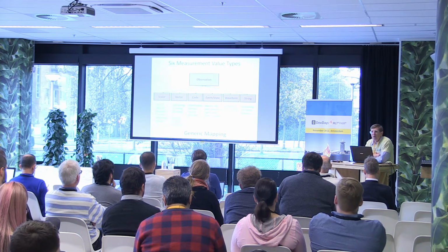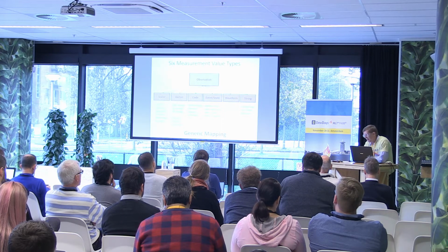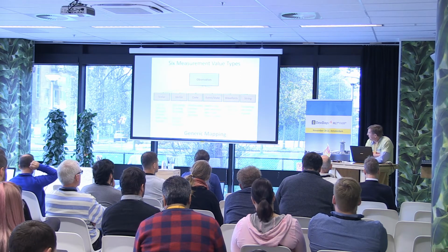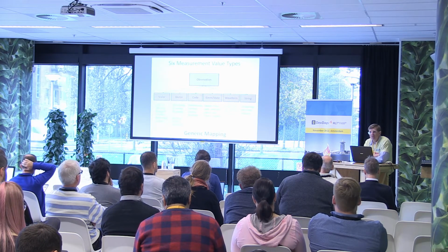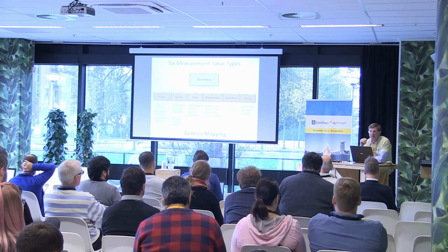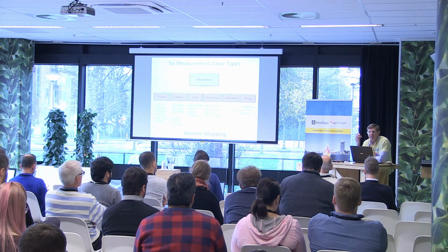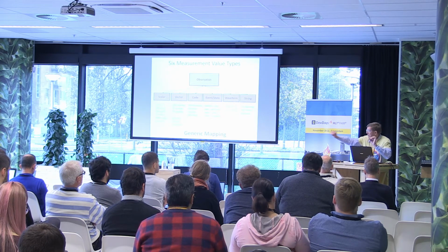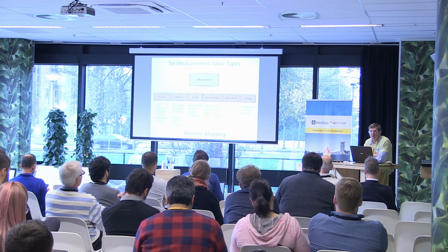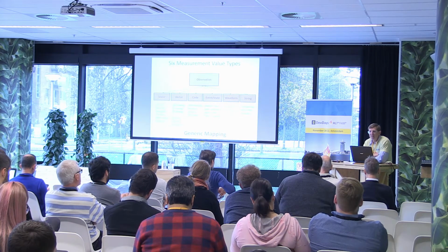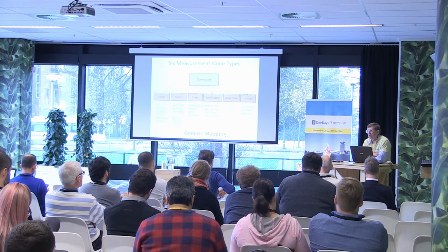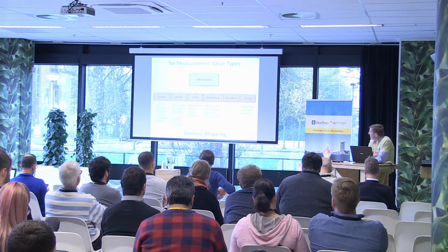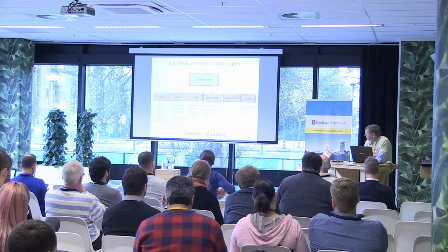And the other type of measurement are waveforms, ECG traces, for example. I've got one here that can take ECG traces, and you can upload those. Those types of measurements are strings of periodic data, and they can be a lot. For example, this thing takes 250 samples per second for 30 seconds, so we end up uploading something like 7,500 samples as a long string of data. Now, you could be really dumb and upload each one of them as an individual scalar, do 7,500 uploads to accomplish the transfer of the data. Not too smart. So every periodic waveform is always mapped in the same way as a waveform.